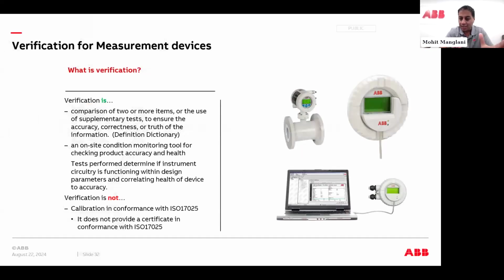Verification is the capability to match the health of the device and correlate it directly to the accuracy. So I'll say this, back in the day, if somebody said, I need to calibrate a mag meter, they had to shut down production or the line or isolate it, whatever it might be. They had to remove the meter out of the line. They had to send it back to a facility that builds mag meters or does calibrations. You'd have to run known flow through it. Obviously, you get a calibration certificate. That's your calibration to make sure that the meter is accurate. Obviously, that's a lot of downtime because you have to have a spare. You have to have downtime to take out the mag meter or use a bypass. Obviously, there's time associated with being down and getting back up electrically, mechanically, etc.